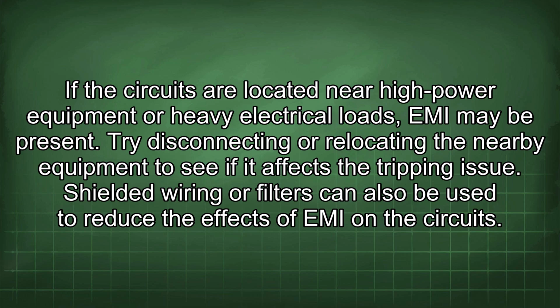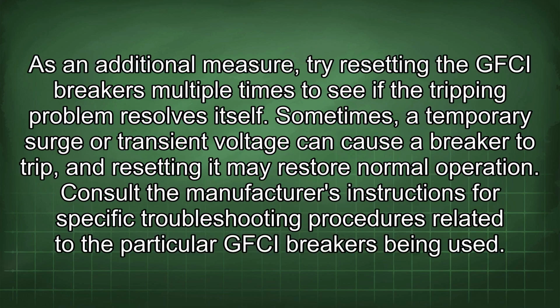Try disconnecting or relocating the nearby equipment to see if it affects the tripping issue. Shielded wiring or filters can also be used to reduce the effects of EMI in the circuits. As an additional measure, try resetting the GFCI breakers multiple times to see if the tripping problem resolves itself. Sometimes, a temporary surge or transient voltage can cause a breaker to trip, and resetting it may restore normal operation.